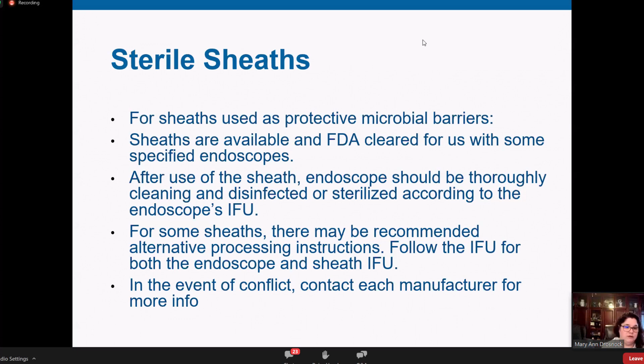Now, for some sheaths, there may be recommended alternative processing instructions, and we say follow the IFU for both the endoscope and the sheath manufacturer to know what to do with them, and contact the manufacturers if there's conflict so that you get validation information and just more data on what you want to do with those. And then we do within ST91 have a section on what to do if you have IFUs that conflict.